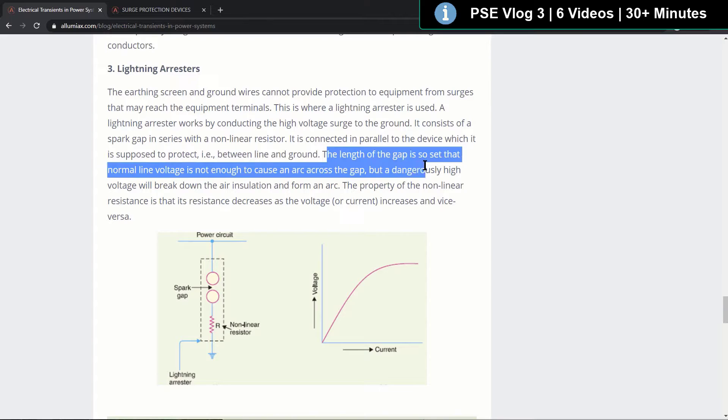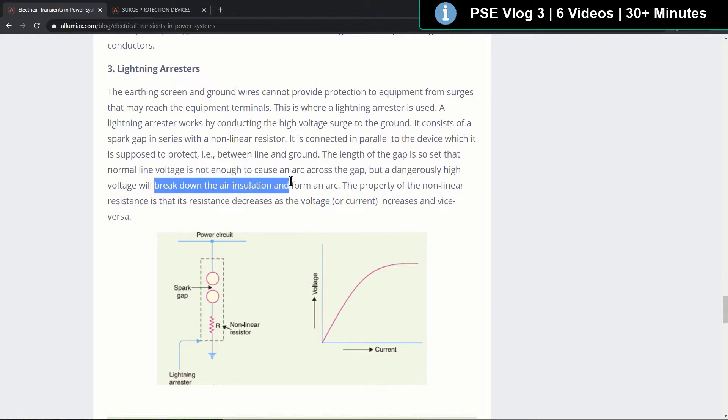The length of the gap is set so the nominal line voltage is not enough to cause the arc across the gap, but a dangerously high voltage will break down the air insulation to form an arc.